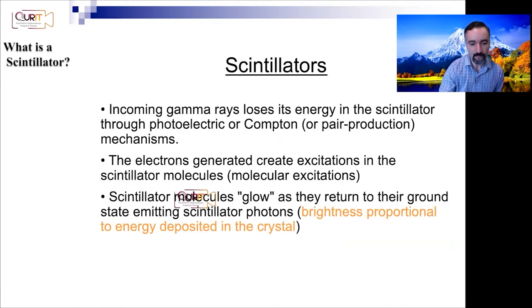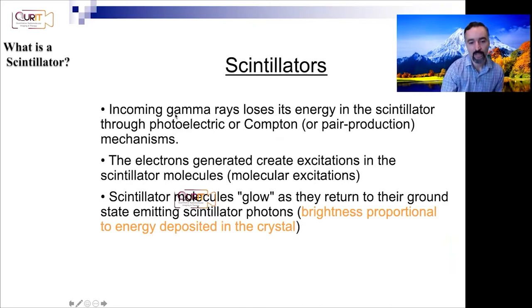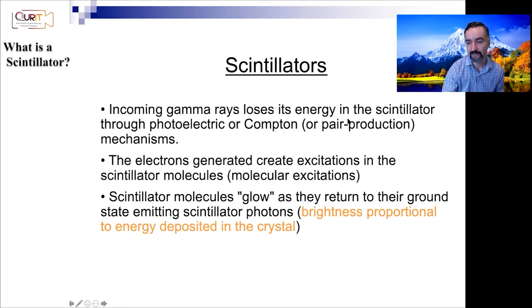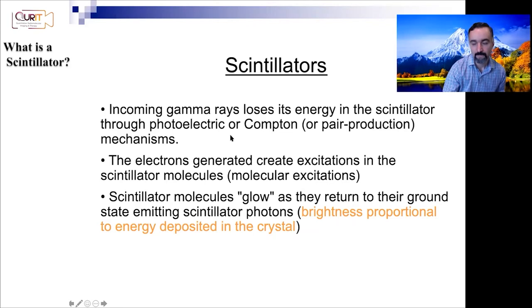Scintillators are essentially trying to process incoming gamma rays. The incoming gamma ray, which is highly energetic — for technetium we're looking at 140 keV — loses its energy in the scintillator. This happens either through the photoelectric effect or Compton scattering. If the incoming energy is very high — more than two times 511 keV — pair production can also be a factor. So at our energies we're dealing with either the photoelectric or Compton mechanisms to absorb the incoming energy.